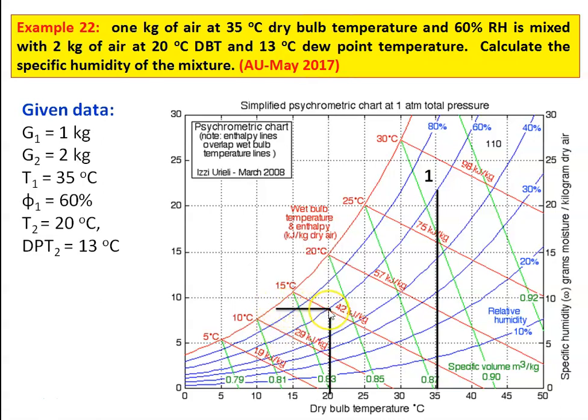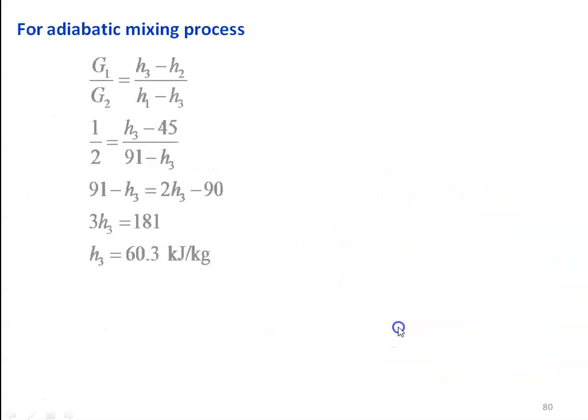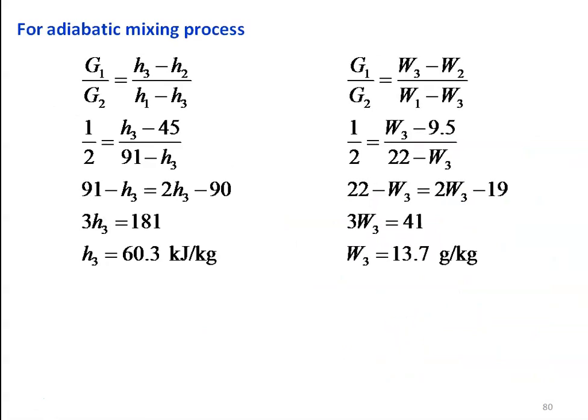Points 1 and 2 form the process line. We take the properties: H1 = 91 kJ/kg, H2 = 45 kJ/kg, W1 = 22 g/kg, W2 = 9.5 g/kg. Using the same equation for adiabatic mixing — G1/G2 = (H3 − H2) / (H1 − H3) — this is obtained by mass balance; you can refer to the earlier lecture for the derivation. Substituting the values and solving, H3 = 60.3 kJ/kg.